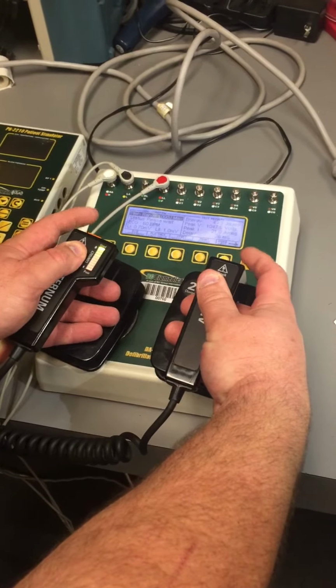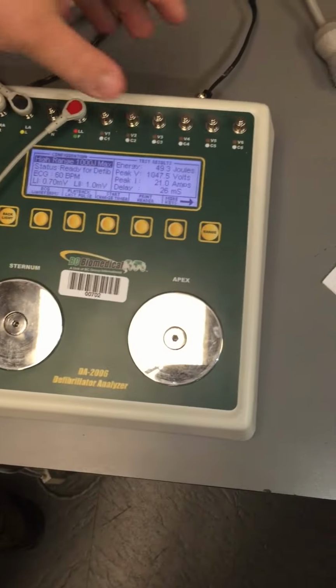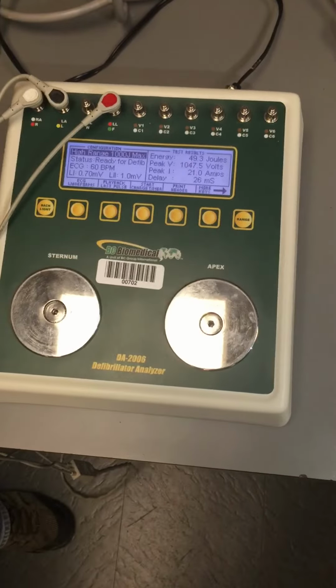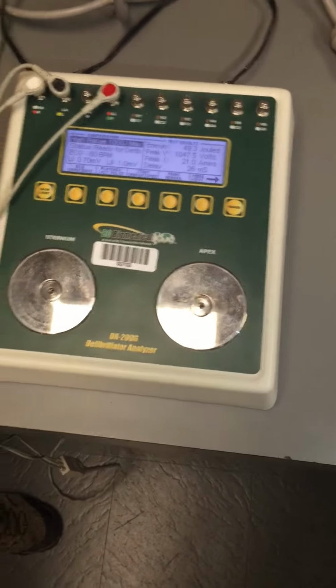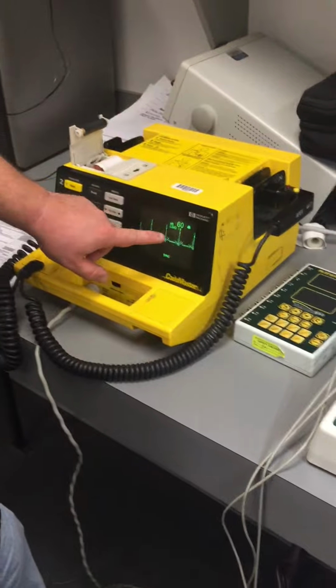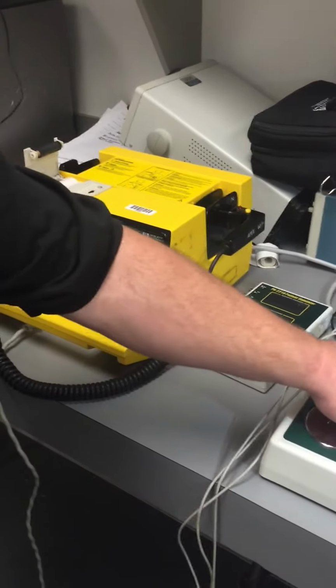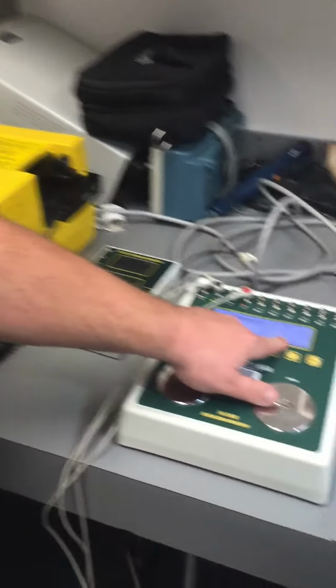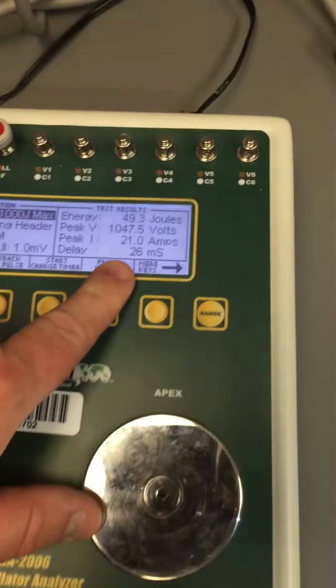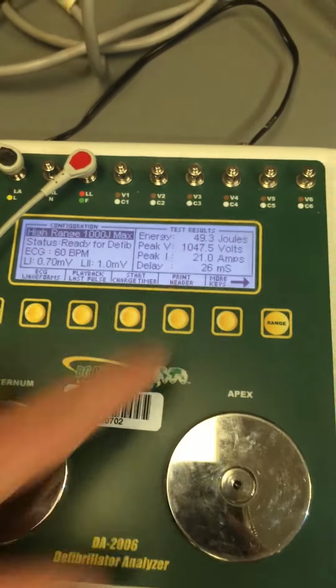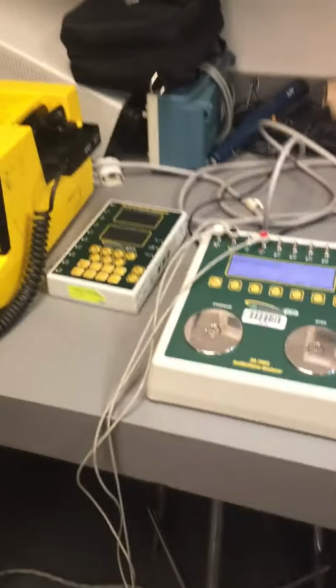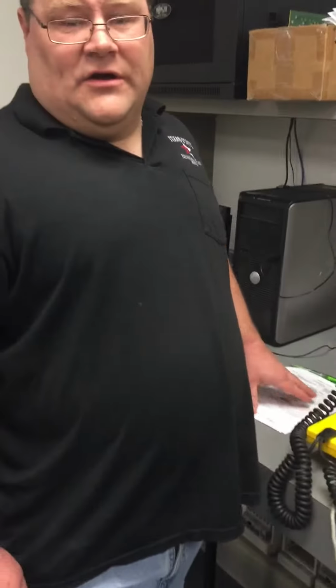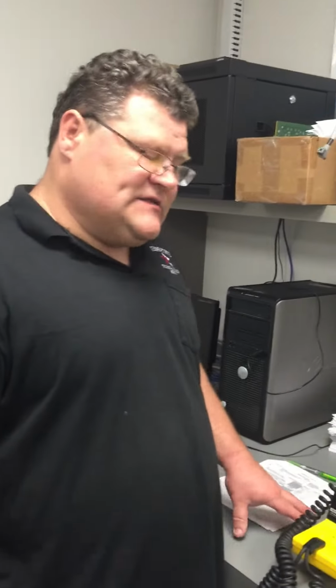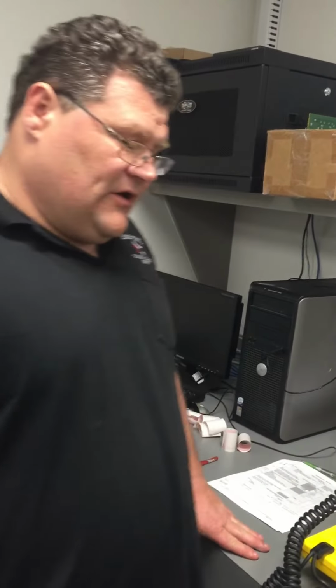Notice when I held the buttons there was a slight delay. It will not fire the defib until it measures the peak of the R wave, right where that dot is. In this case, it delayed 26 milliseconds from the peak of the R wave, and that is within our window. Our window is 20 to 30 milliseconds, so this device is actually functioning very well for us.